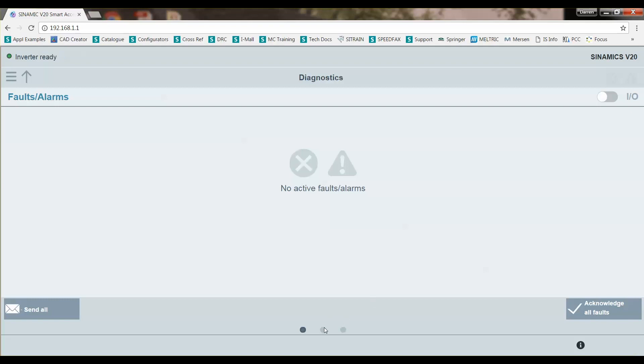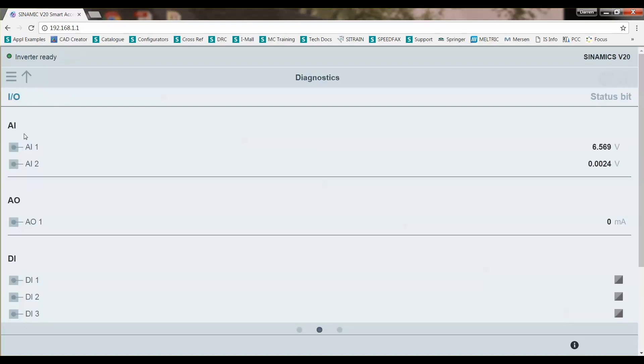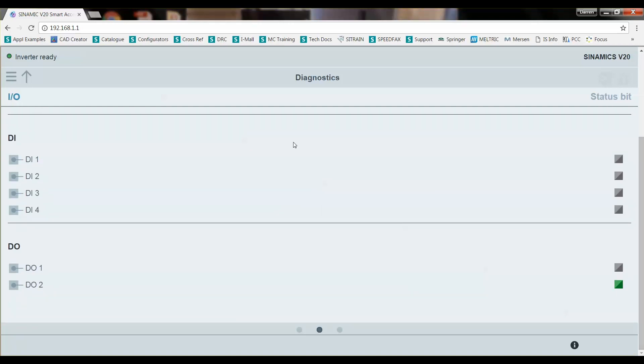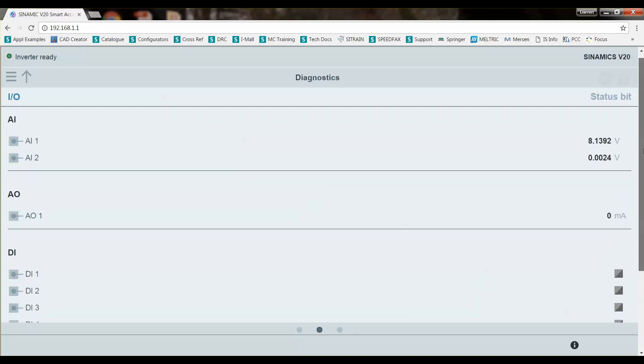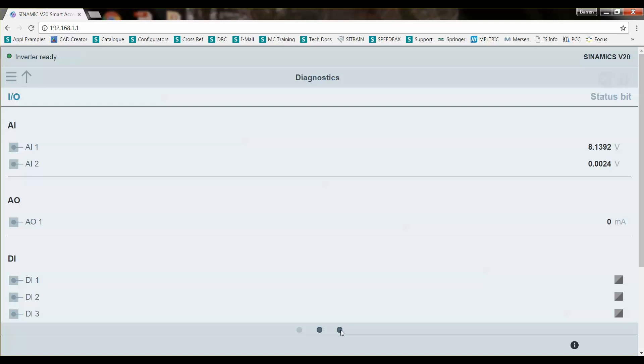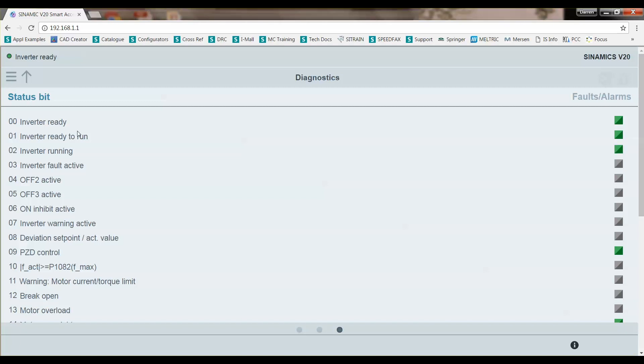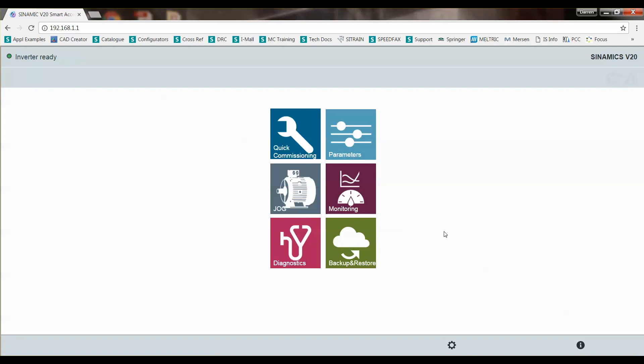I can go to this next little page and I can see the status of my analog inputs. So I can dial it down, less voltage, zero to 10 signal, dial it all the way up, 10 volts. I can also see the status of my digital inputs, digital outs. So digital input one high to turn it on, two high to go reverse. So we can monitor digital inputs and outputs and analog inputs and output that way. And then we have a status word. So we've got a green indicator here saying inverter's ready. Turn it on. Now we've got an indicator here, green saying the inverter's running. Turn it off. Now just an inverter ready again. So that shows the different pages of the diagnostics.